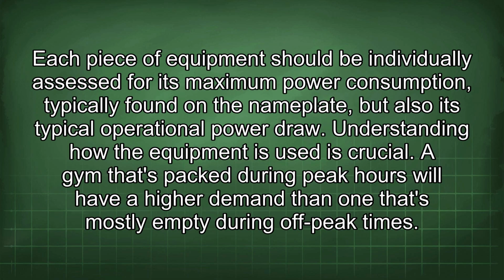Each piece of equipment should be individually assessed for its maximum power consumption, typically found on the nameplate, but also its typical operational power draw. Understanding how the equipment is used is crucial. A gym that's packed during peak hours will have a higher demand than one that's mostly empty during off-peak times.